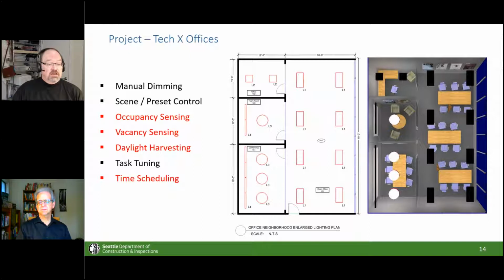You're also going to need manual control in there at the very least, preferably manual dimming. You'll also need or want occupancy or vacancy sensing. With occupancy sensing, remember, you can only bring that lighting up to 50% light output automatically; with a vacancy sensor, you press the button and the lights go on.